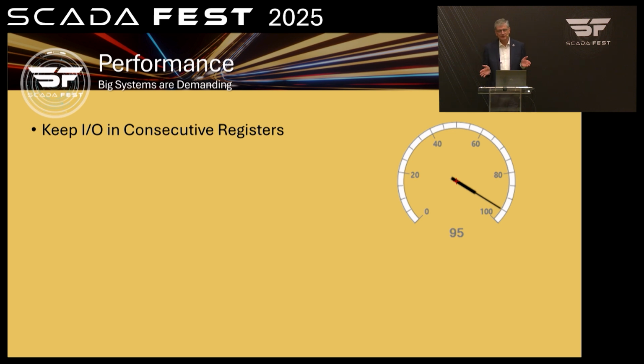Another related kind of problem is that although they may be putting them in the same block, they may say I want to read these at 5 seconds, and I'll read these once a minute. Every time you put a different timing for each piece of it, it takes - you've got to read the 1 minute once every minute, and the 5 second ones every 5 seconds, and they're all kind of mixed together. It's just as bad as having them fragmented. So try to keep the polling rates consistent across consecutive registers if you can. It makes a huge difference to the performance of the communication. And it's not us, it's really the PLC and the communication link that's the bottleneck. You can optimize that by getting things grouped together nicely.